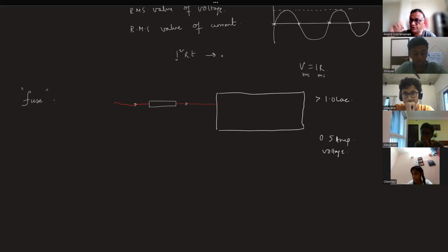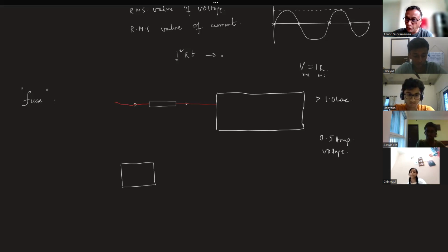But suddenly, sometimes what happens in the distribution is no fault of yours. In your distribution, meaning the BESCOM side, there will be a surge - a voltage surge will be there, it's like a fault. So suddenly you will have high voltage and high current available in your circuit. So in many places the electrical safety devices are put - in the beginning itself you may trap it, or you will have it within your room where circuit breakers are placed. You can detect it in many places - it will trip, sometimes in the room, sometimes outside, wherever it is detected. So what happens is, if suddenly there is a surge, more current is flowing.